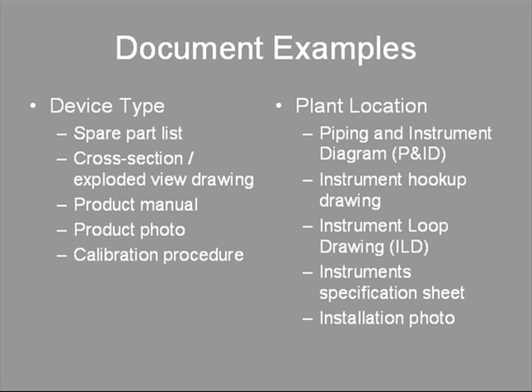Device type documents from the device manufacturer include spare part list, cross-section or exploded view drawing, product manual, product photo, and calibration procedure. Device type documents are the same regardless of which plant the device is used in. Plant location documents from the project engineering company include piping and instrumentation diagram (P&ID), instrument hookup drawing, instrument loop drawing, instrument specification sheet, and installation photo. Plant location documents are the same regardless of which type of device is used.